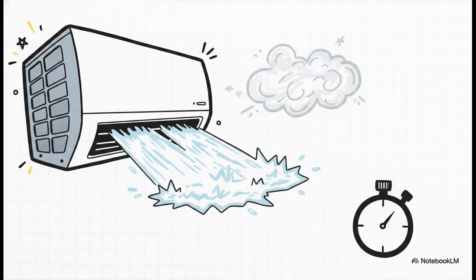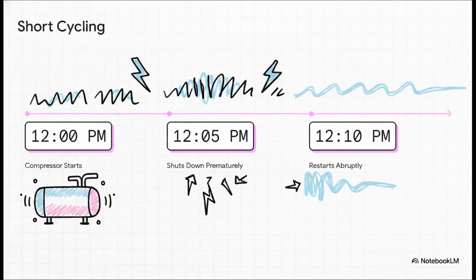And here is the hidden trap in system design. If an AC unit is oversized for the space, it blasts the temperature down very quickly and then abruptly shuts off. It satisfies the thermostat's temperature requirement way before it has time to remove that sticky, latent moisture from the air. You're just left standing in a cold, clammy room, feeling like you're inside a damp cave instead of a modern office. This kind of rapid cooling leads directly to a highly destructive mechanical issue known as short cycling.